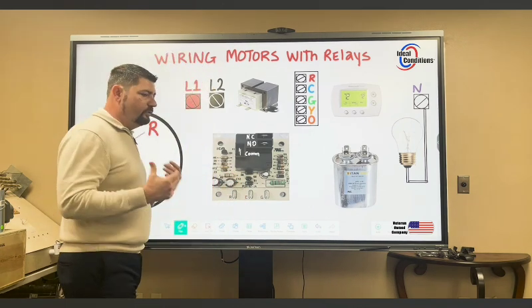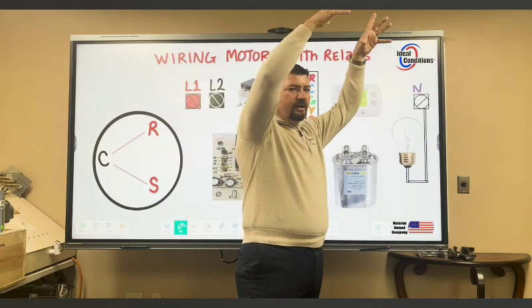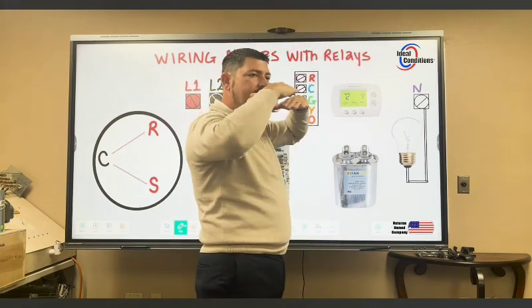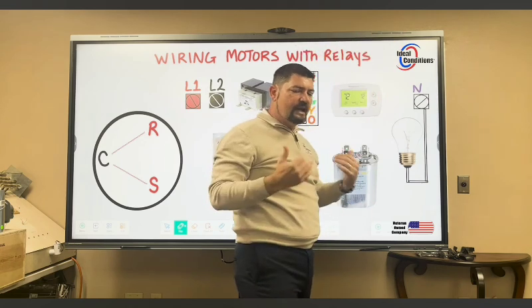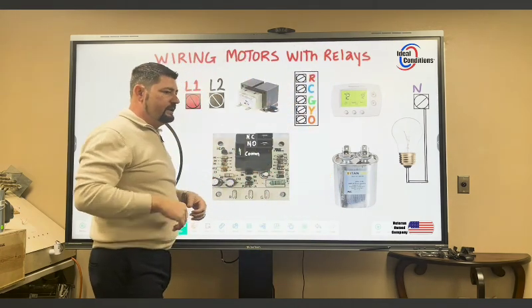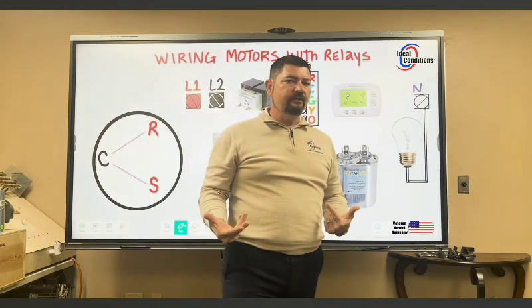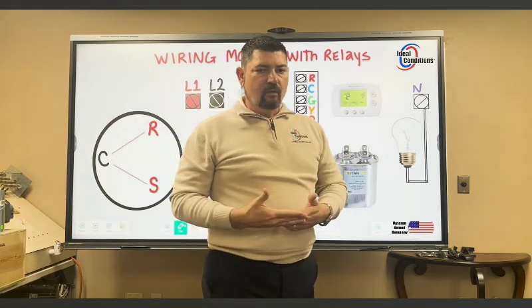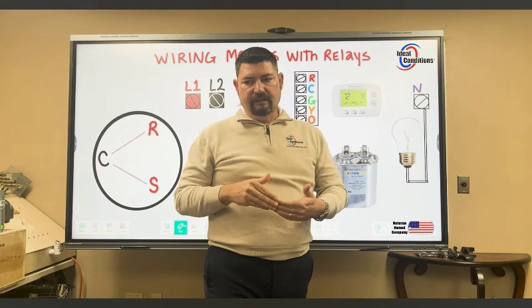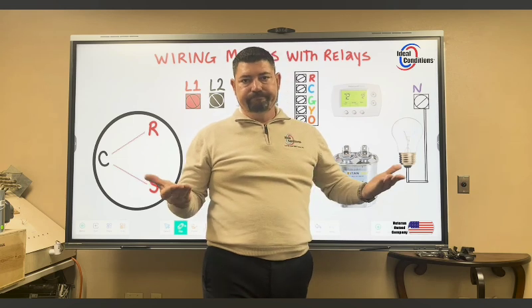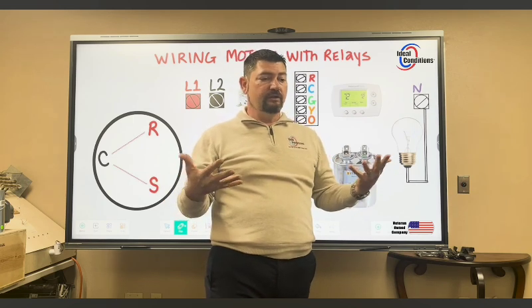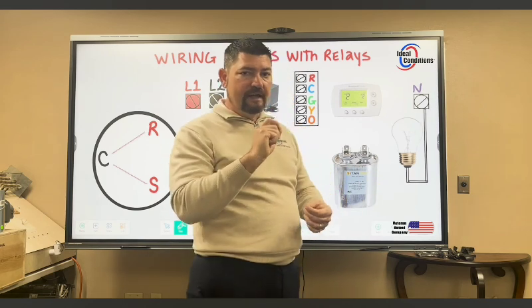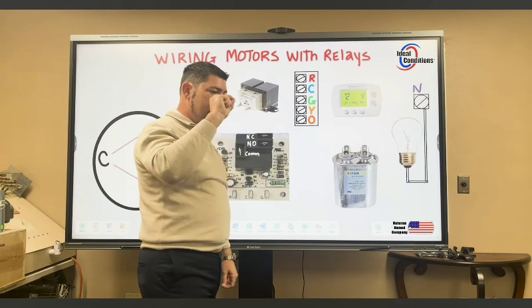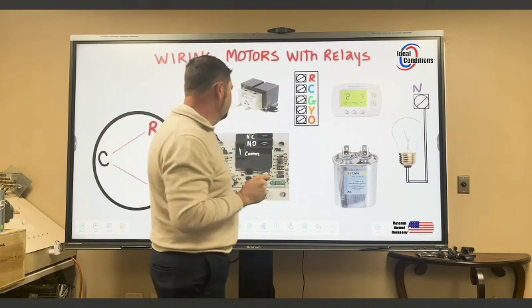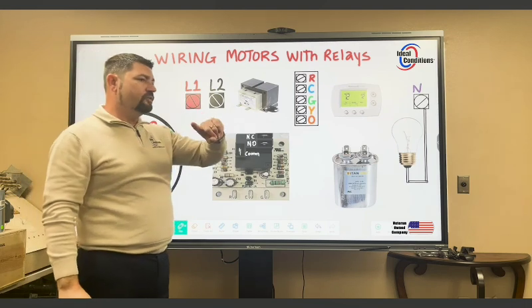Okay, we have L1 and L2, so out there in the field where you're working, you're typically working above your head. If you're working in an air handler, they're never really at eye level. So sometimes you're standing on something, trying to get in there. Sometimes you can just reach it just fine, but you have to keep in consideration when you're trying to rewire something, you can't just go off of colors, you can't just go off of wire gauges, because sometimes you have a lower wire gauge that is typically wired to something that is low voltage or high voltage, and that American wire gauge number may not be printed on there, so you don't want to just go off of the insulation and how thick it feels or anything like that. Instead, you want to verify where one end of that wire is going to.